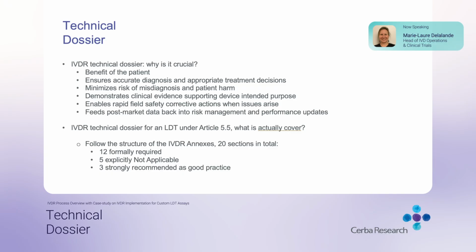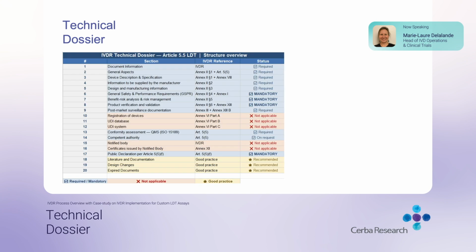No device registration, no UDI, no notified body here, because we are not placing the device on the market. And 3 are not legally required, but strongly recommended as good practice: literature documentation, design change record, and version control of expired documents. The next slide shows the full table.